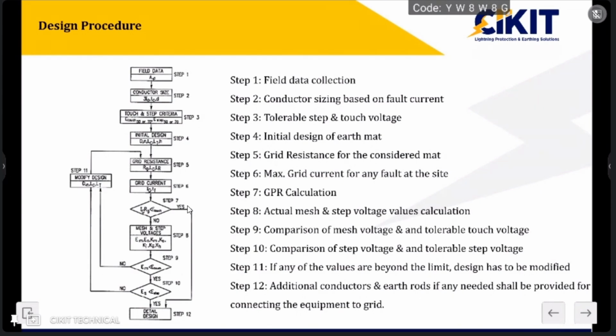If you closely observe these 12 steps, we are not at all considering the earth electrode, that is, the earthing resistance value or grid resistance value. Many people consider that the grid resistance value should be less than 1 ohm, but that is not the case. The standard does not consider this resistance value for evaluating the design procedure. They consider two important parameters, step and touch voltage. If the step and touch voltages are within the limit, then the design can be considered safe, and it is not mandatory to ensure that the grid resistance value is less than 1 ohm.